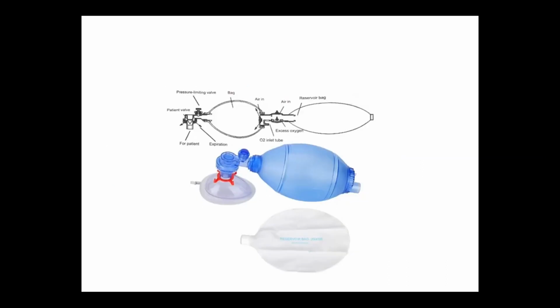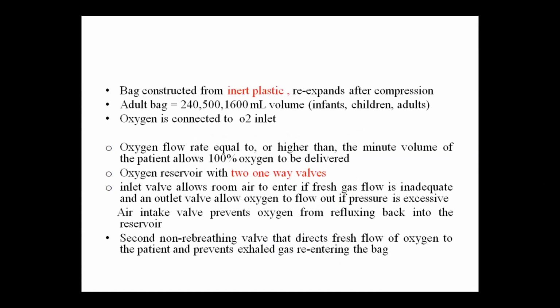The part where the oxygen is connected is away from the patient, opposite to the patient. Here we attach the oxygen; there is an oxygen inlet and an attachment for the reservoir bag. The oxygen flow rate should be equal to or higher than the minute volume of the patient to allow 100% oxygen to be delivered.